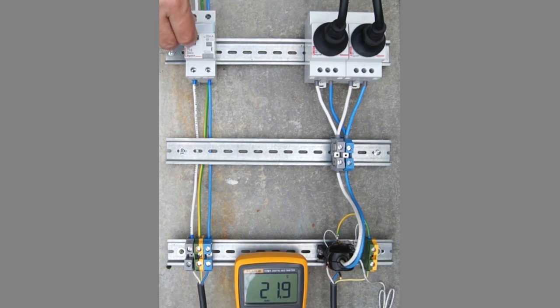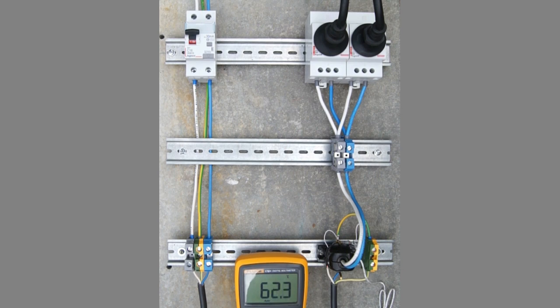Now let's see the protection action live. Turn on the power. The temperature of the socket outlet is rising rapidly as in previous experiments. No sparking is also visible. Let's speed up the playback. We get the required reaction at 84 degrees. Next the connecting parts cool down. We get additional information about the causes of triggering by the RCBO indicator. Yellow color means that there was a ground fault.